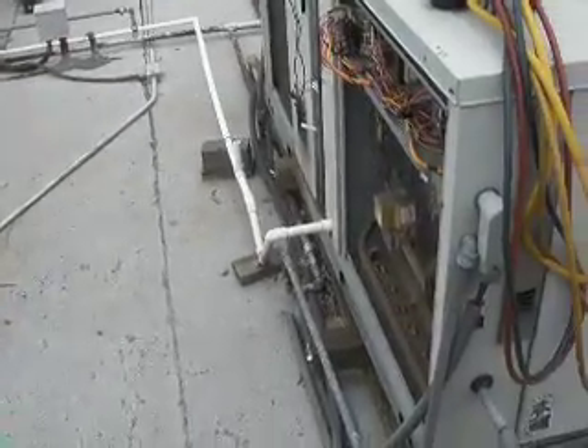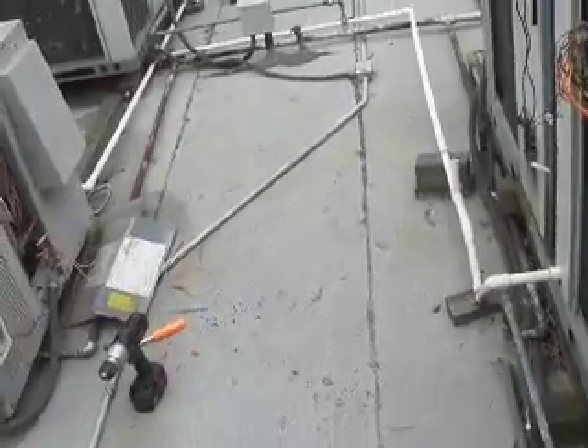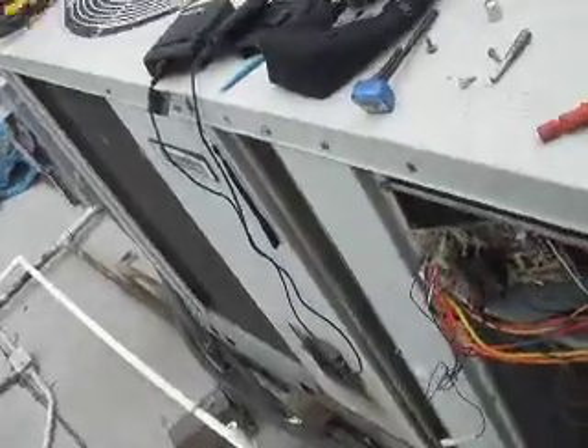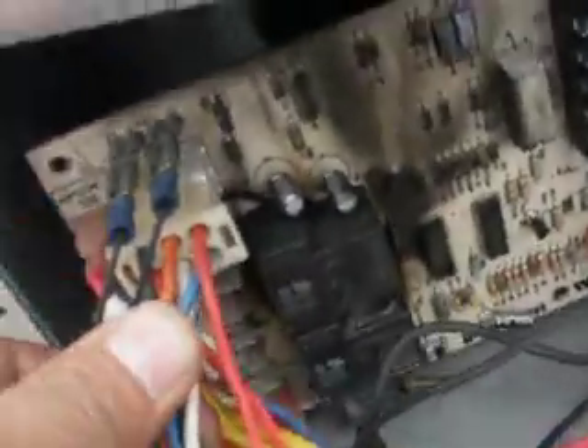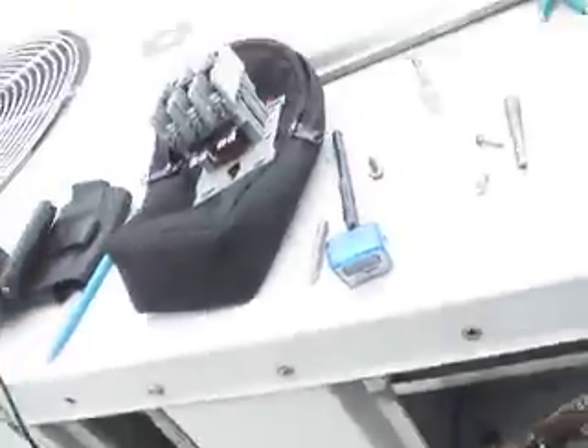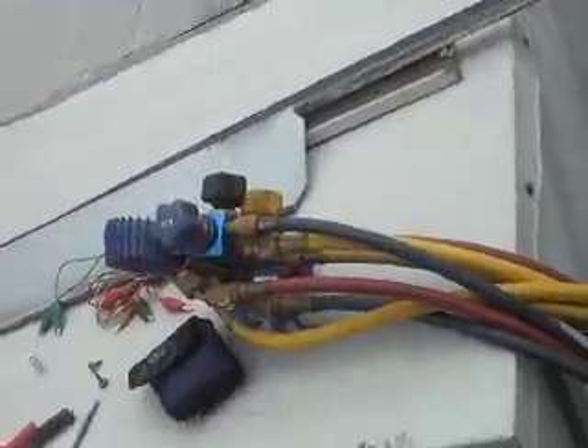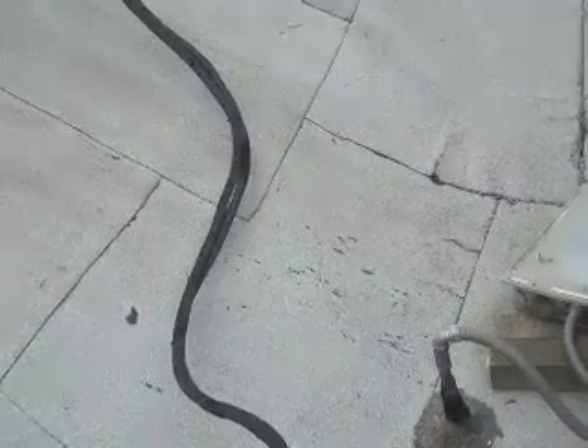Like I said, we just got up here diagnosing everything. Here we go. We got a toasted control board because the blower motor went out. And this one right here, the blower motor's out on this one. It's all iced up because the compressor's running and running and running, and of course there's no heat load on the coil.